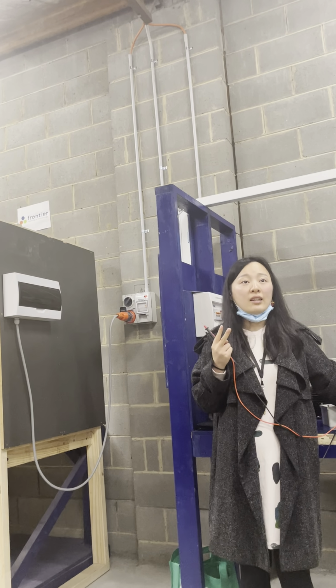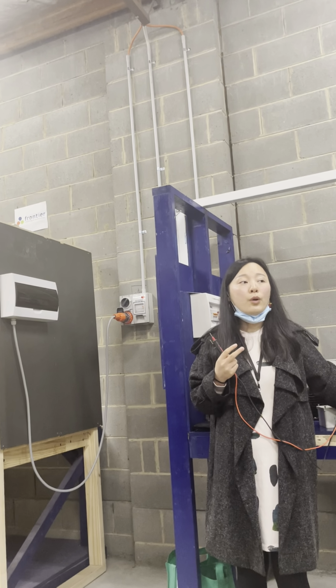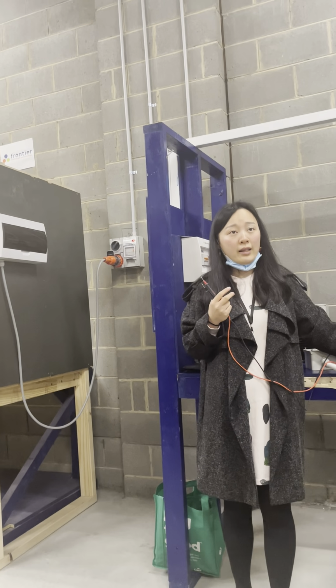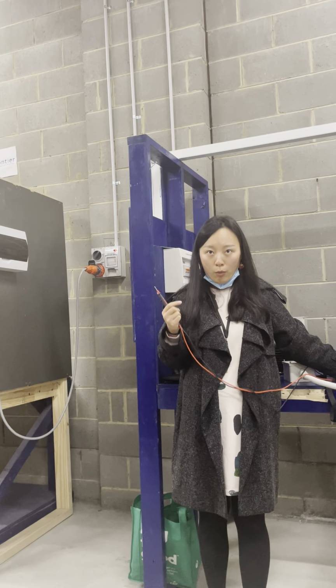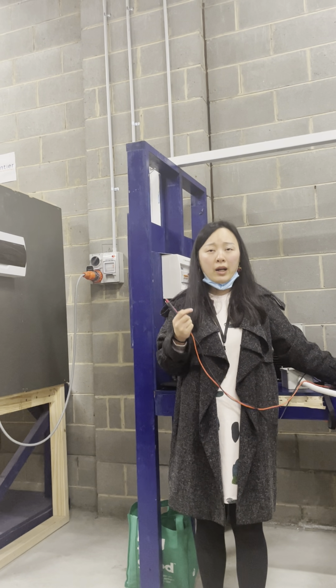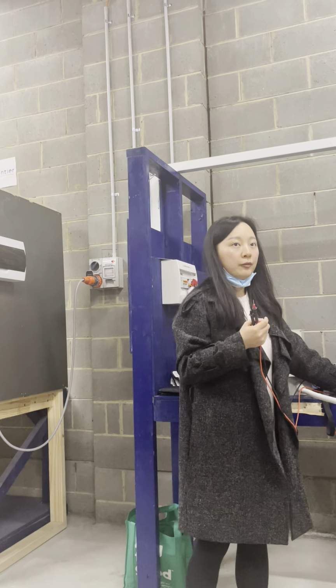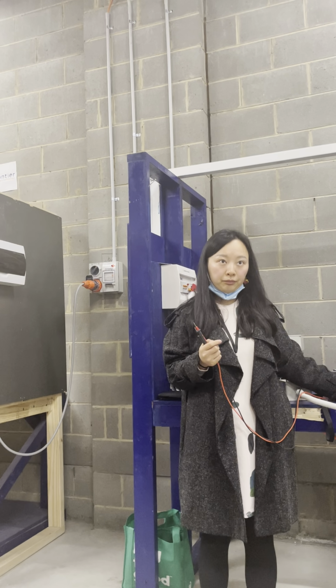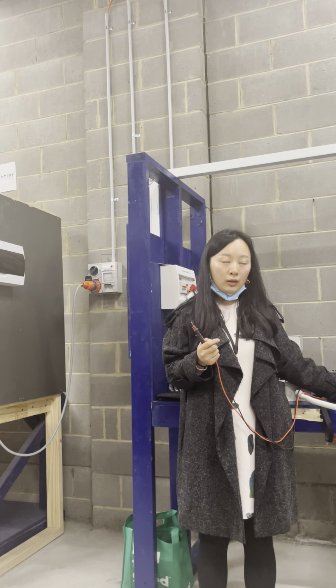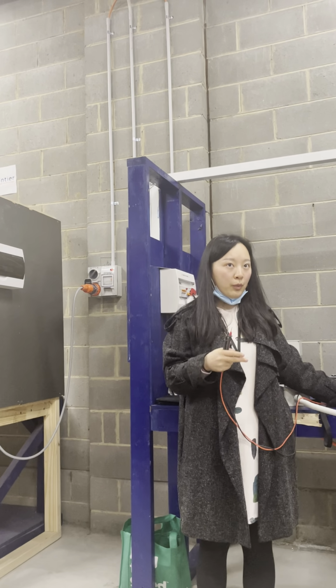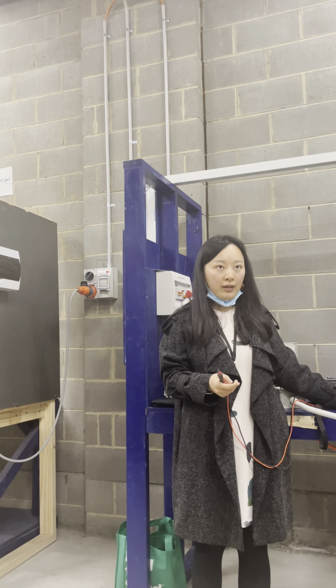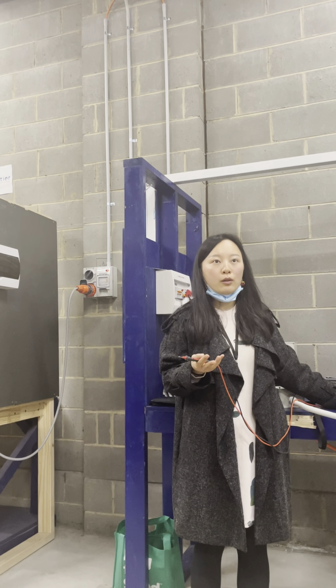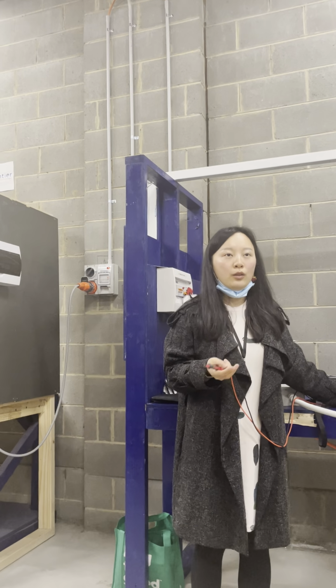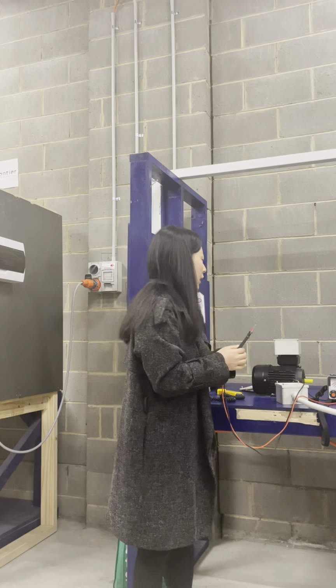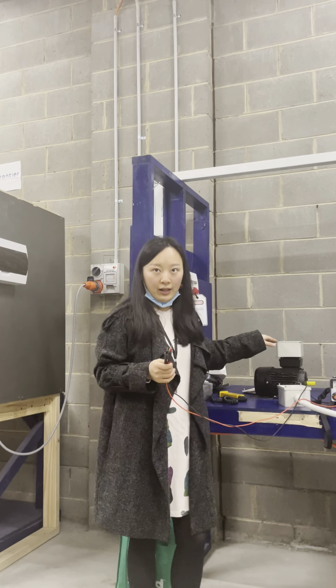Those two numbers you must remember. Those will come out of the 4 questions he will ask you. So 0.5 ohms for the continuity, 1 mega ohm for the IR test. So it needs to be greater than 1. And for continuity, less than 0.5. Yeah, correct. Ideally, you would expect 0 ohms, but nothing is perfect. You only get some sort of value. So now it passed the IR test, correct?